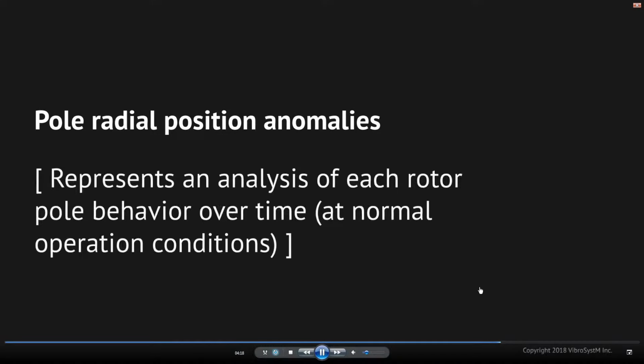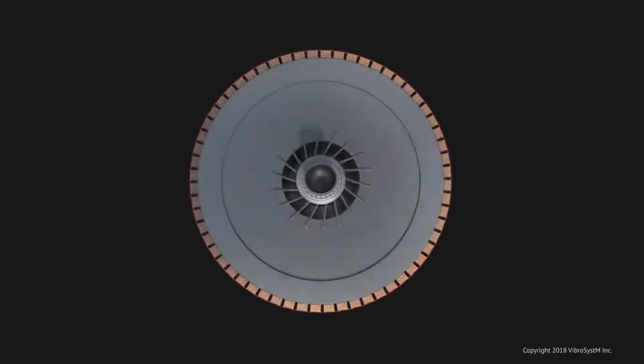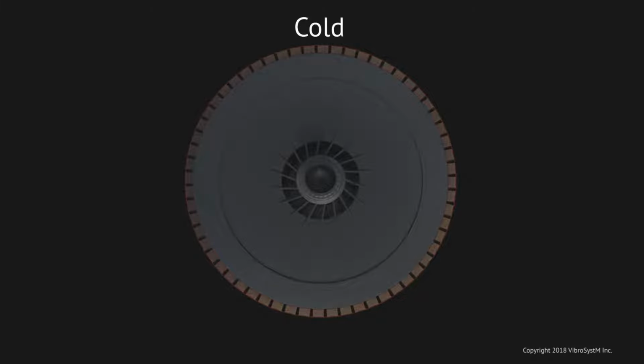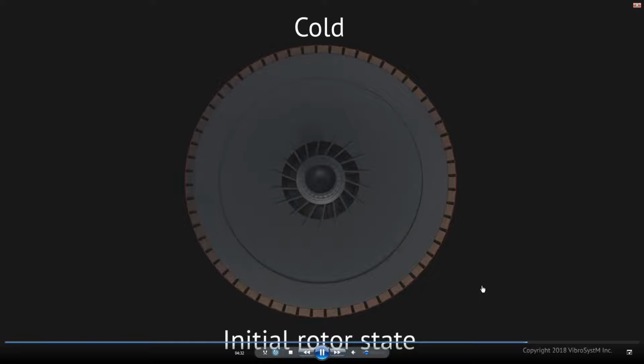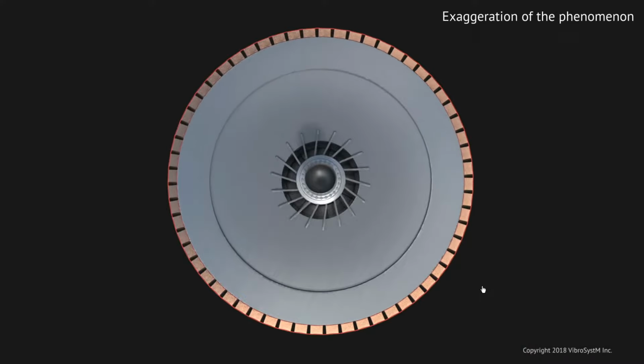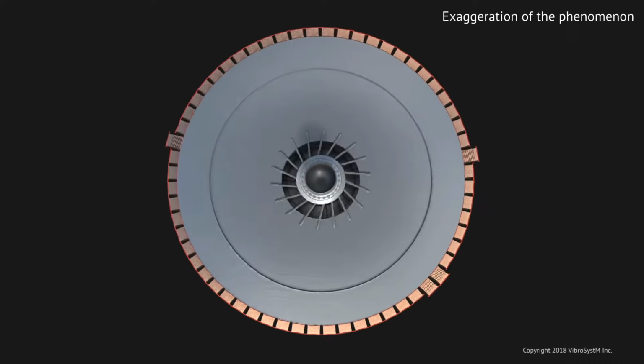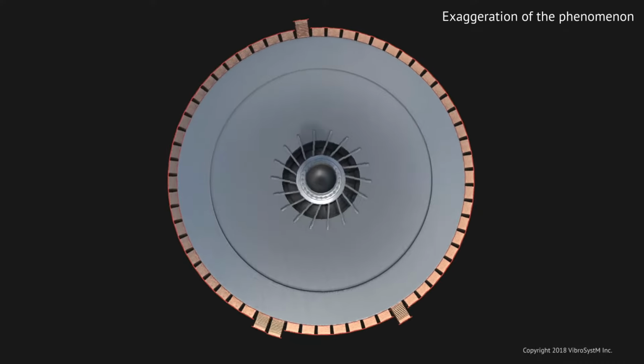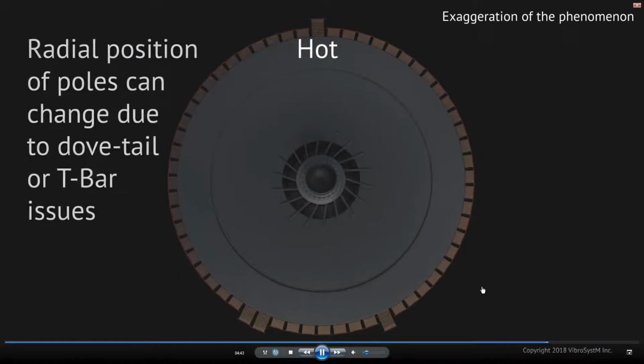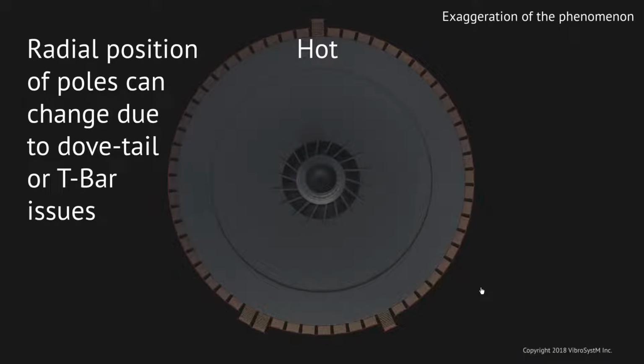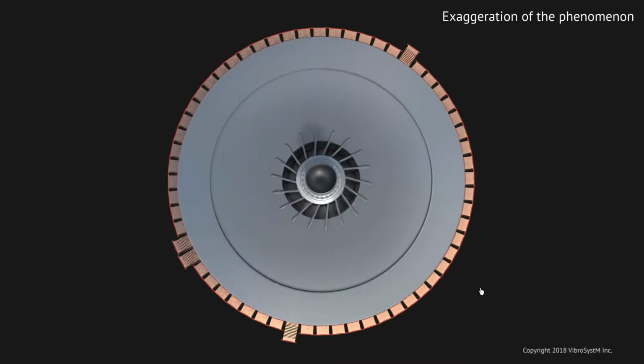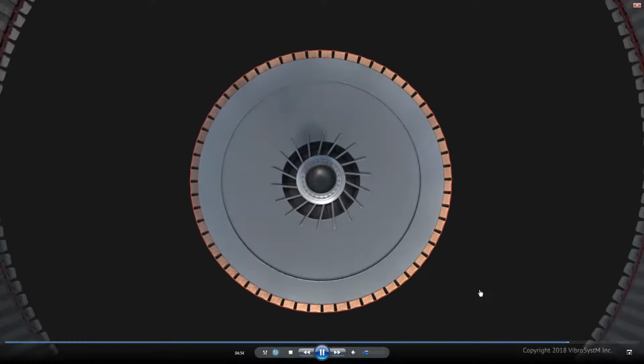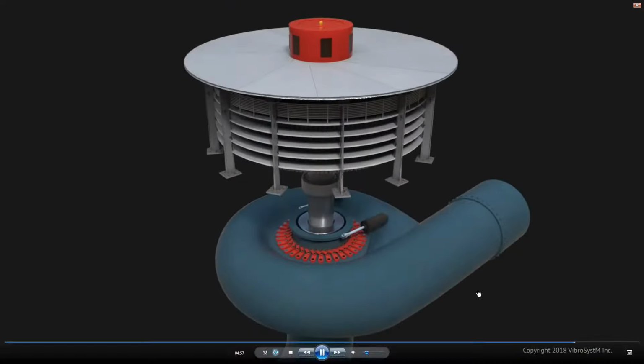Pole radial position anomalies, that represents an analysis of each rotor pole over time at normal operating conditions. Okay, so in this case, we'll look at individual poles and see if their radial position is beyond a certain guideline from one pole to an adjacent pole and so forth. It's quite rare to see a pole sticking out a lot, but it is quite common to see poles that are sticking out more than they should, and that usually requires some action to be taken to fix that before it becomes loose and actually hits the stator.